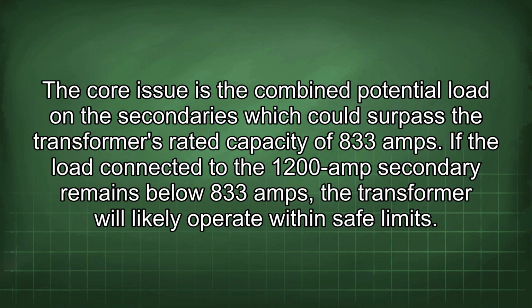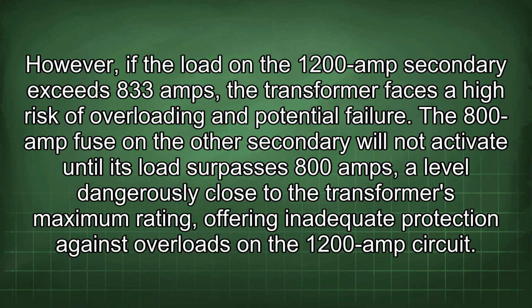amps. If the load connected to the 1200 amp secondary remains below 833 amps, the transformer will likely operate within safe limits. However, if the load on the 1200 amp secondary exceeds 833 amps, the transformer faces a high risk of overloading and potential failure. The 800 amp fuse on the other secondary will not activate until its load surpasses 800 amps, a level dangerously close to the transformer's maximum rating, offering inadequate protection against overloads on the 1200 amp circuit.